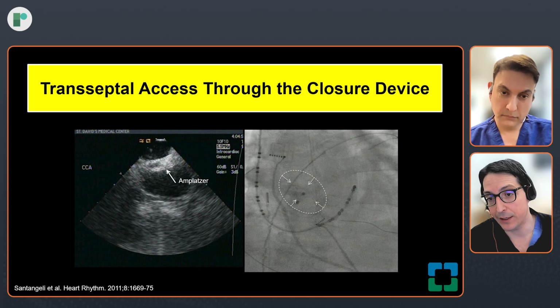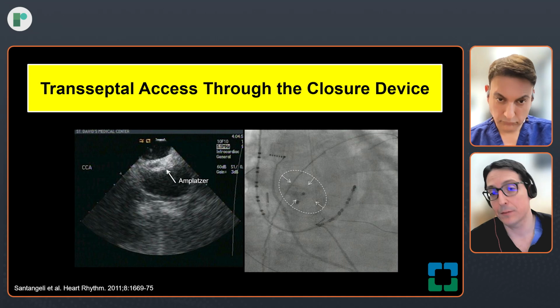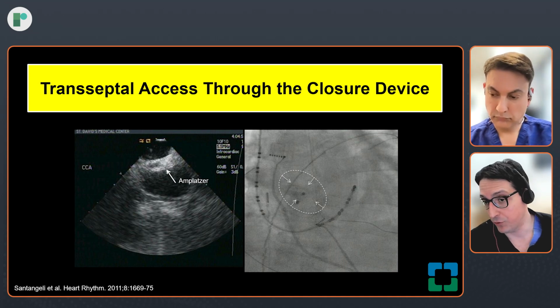If you want to do this, again, you have to be at the periphery, and you always have to make sure you're not close to the central knob of the device where the mesh becomes very dense and almost impossible to perforate through. Perforation is done here with a standard needle because radio frequency really is not able to penetrate through metal because it gives you impedance issues, impedance mismatches.